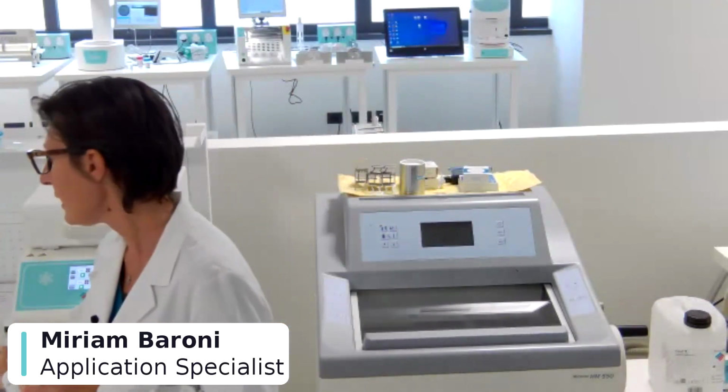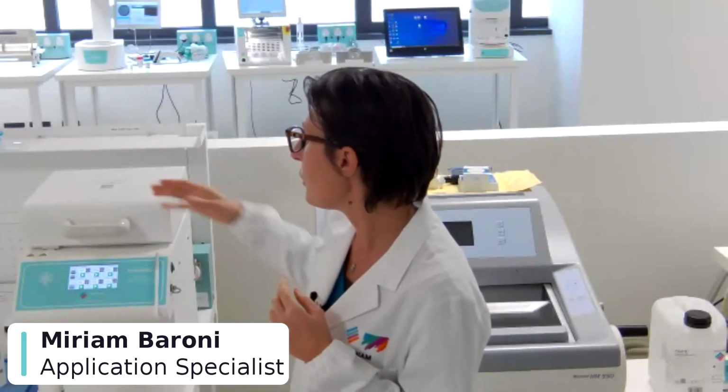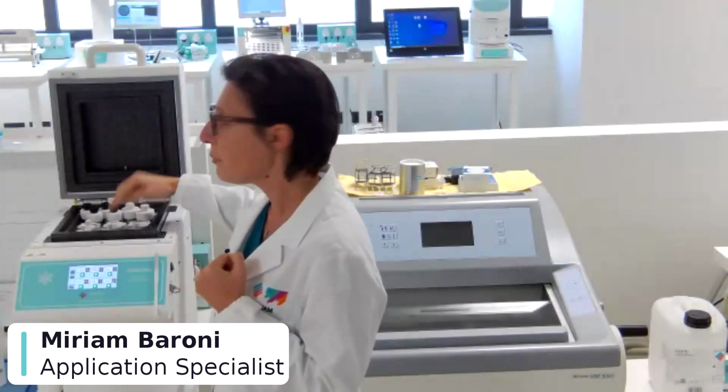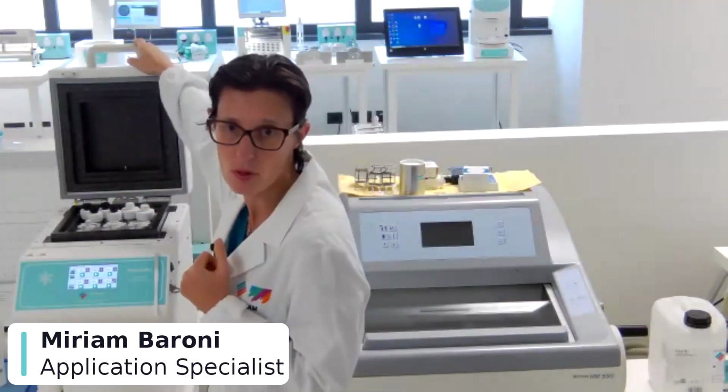And also the link between the tissue during the freezing is much better. Another reagent that we use in the PrestoChill is ethanol to clean the mold between two different samples. So before doing a freezing, we suggest to clean the mold well with ethanol, with paper, and moisten it with ethanol, in order to avoid cross-contamination between samples, and also to avoid the presence of frost inside the mold. Other reagents that we use are for cleaning the instruments.